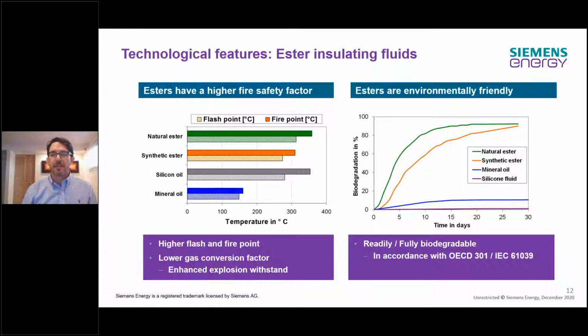I think the best way to measure that is biodegradation. And you see in this chart on the right-hand side the time in days it takes to biodegrade. The line at the bottom on the x-axis is silicone. So silicone fluid doesn't biodegrade at all. Then we see mineral oil biodegrading less than 10% after 30 days. But esters, both natural and synthetic, biodegrade close to 90% after only 30 days. So this is the key topic here, measuring biodegradation in time, in days. And there are some standards and guidelines on how to do that: OECD and IEC 61039.